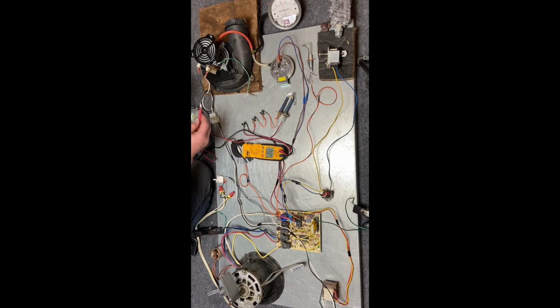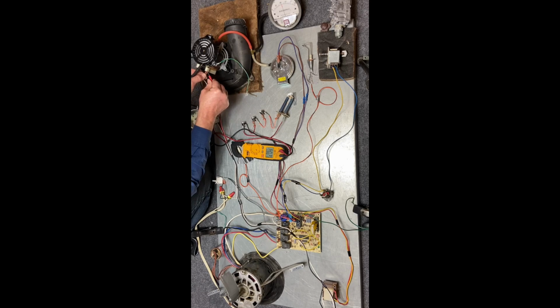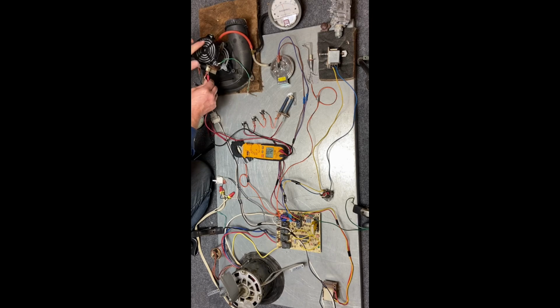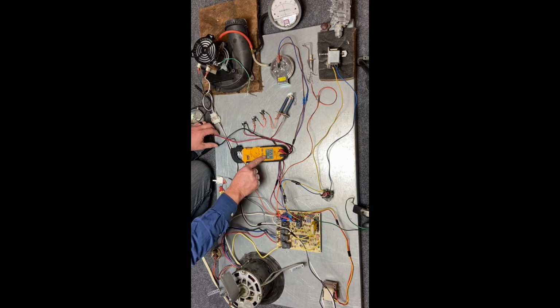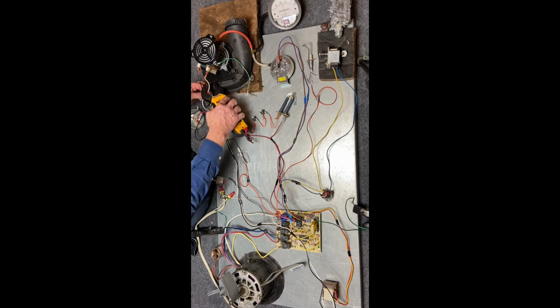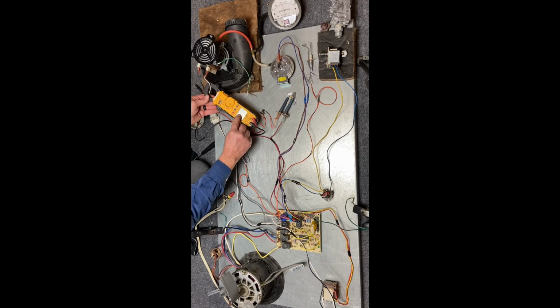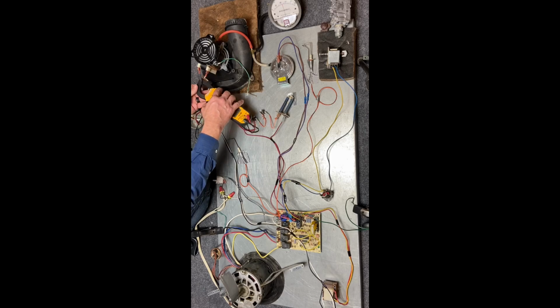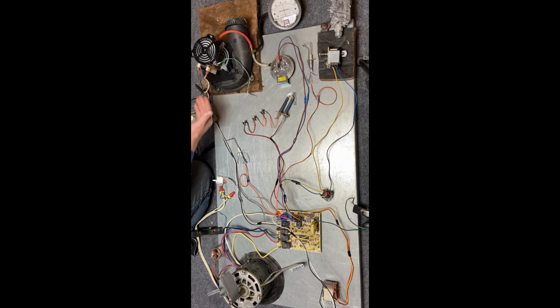Top number is amps. So the voltage to this unit, if I can pull these wires back a little bit and check voltage to our motor. So I'm getting 123 volts to the motor, and this motor is pulling 0.4 inches of water column vacuum through the heat exchanger. I can also check the amperage on this motor. The top number is going to be amps, and if I clamp it around this wire here, I'm reading 1.4 amps, and if I clamp it around the other wire, 1.5 amps. It's pretty close to the same, so I know that my amps are going through here.